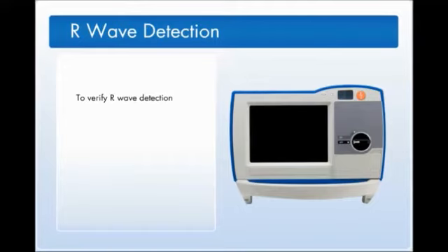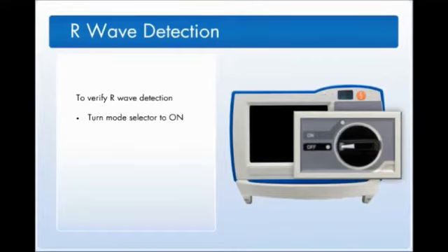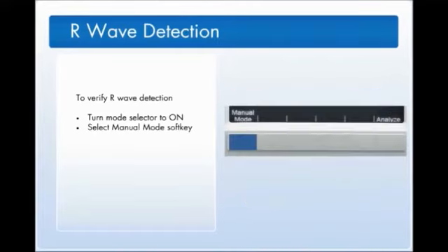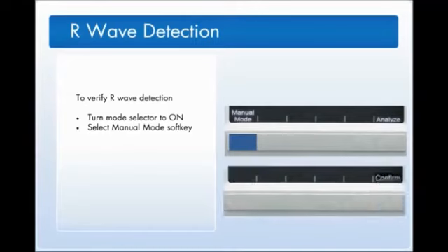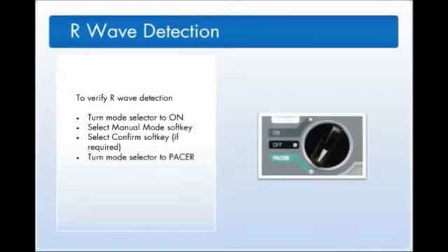Before you begin pacing your patient, you must first verify proper R-wave detection. Convert the R Series Plus to the manual mode. First, turn the mode selector to On. Press the manual mode soft key. Then press the Confirm soft key. Then turn the mode selector to Pacer. The Pacer door will drop open to display the knobs.